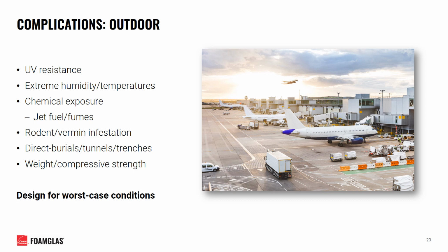may prove critical. Other important questions to ask include, will your material withstand burrowing activities of any local rodents or vermin? For direct burial systems, will materials withstand the compression load of soil backfill? If in high traffic areas, will materials withstand mechanical damage from pedestrian traffic or simply from the elements? Once again, the worst case conditions for your specific system should be determined and designed around.